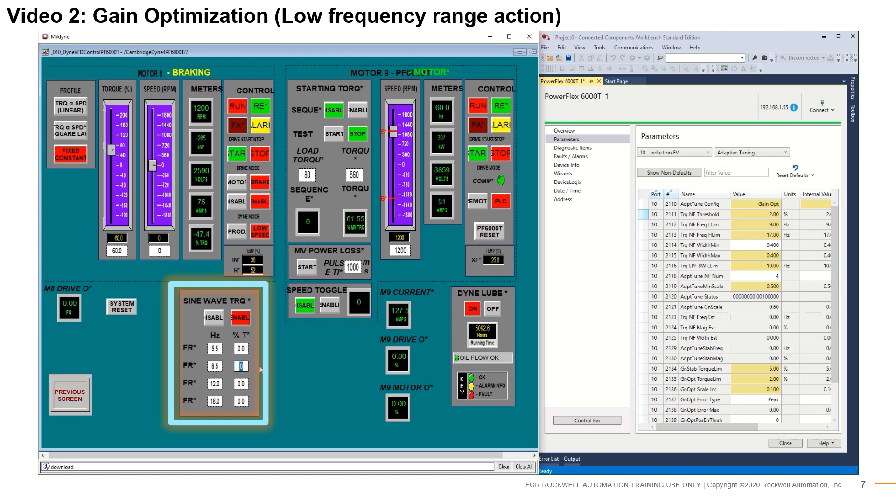Now let's toggle the sine wave injection on and off and observe the gain scalar. It is observed that in the absence of low frequency components, adaptive tuning up-tunes the gain. In the presence of low frequency components, adaptive tuning detunes the gain. This persistent auto-optimization allows the control loop to always operate at the optimal gain setting.